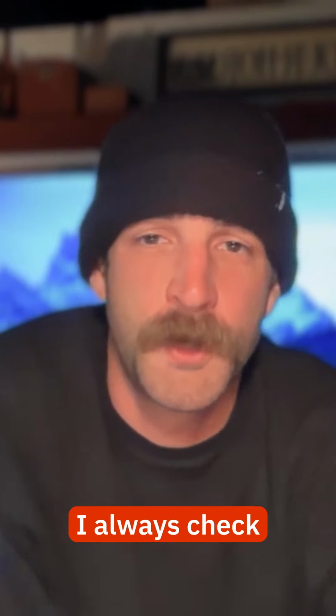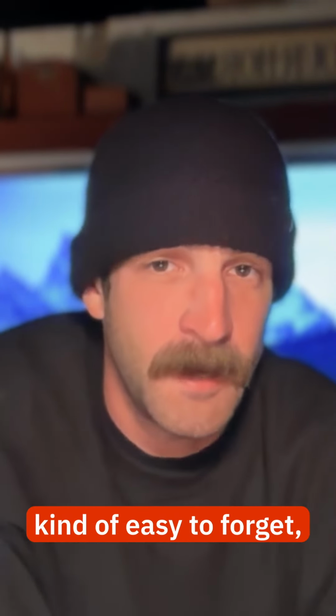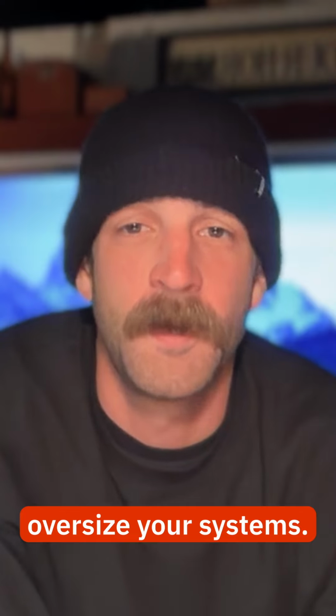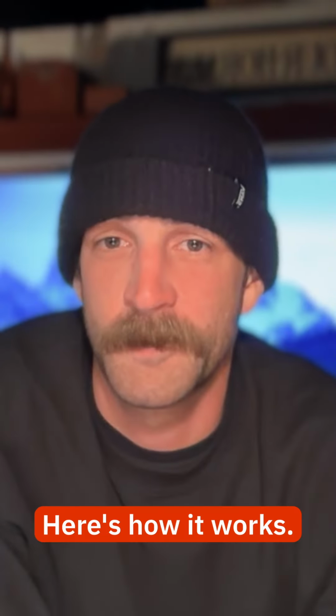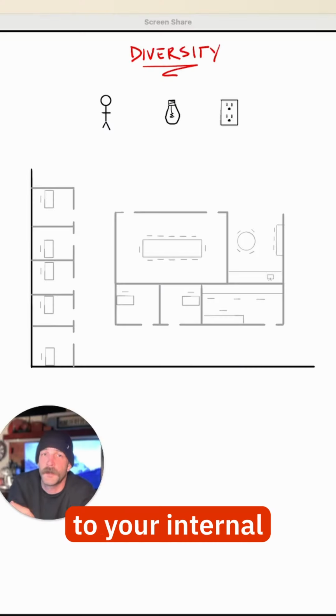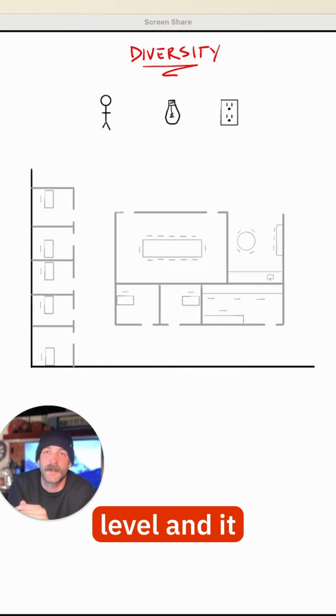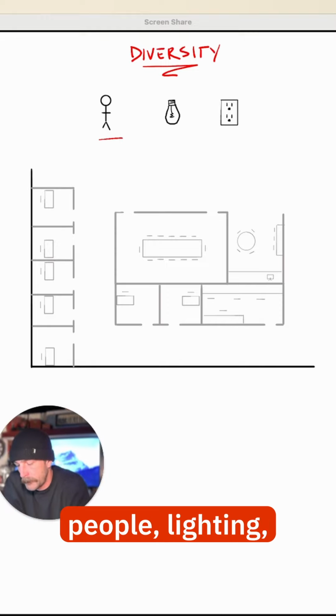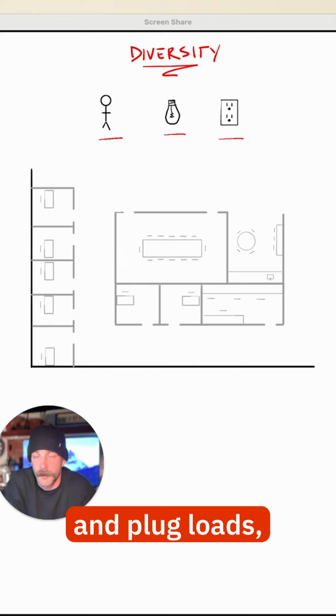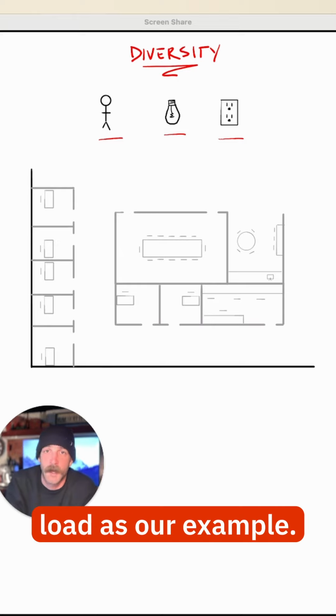There's something I always check before finalizing load calcs, and it's kind of easy to forget, but if you miss it, you'll likely oversize your systems. Diversity. Here's how it works. Diversity is a fraction applied to your internal loads on the system level, and it can be applied for people, lighting, and plug loads. But let's use people load as our example.